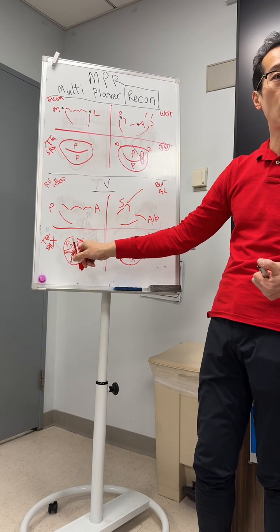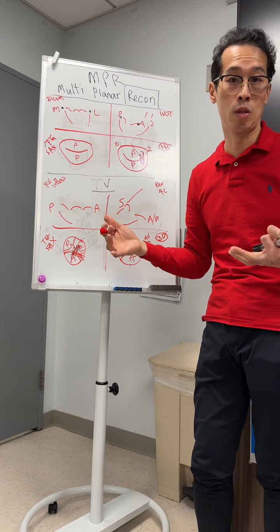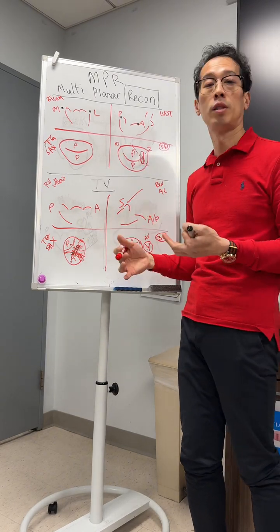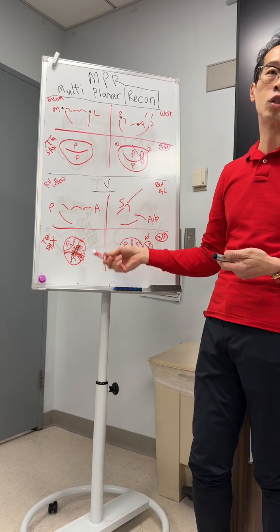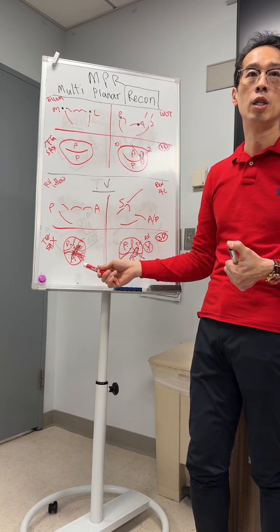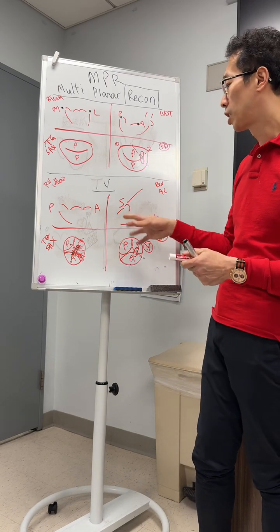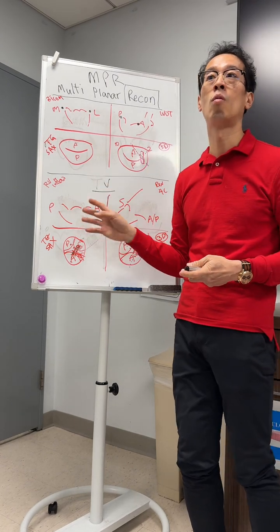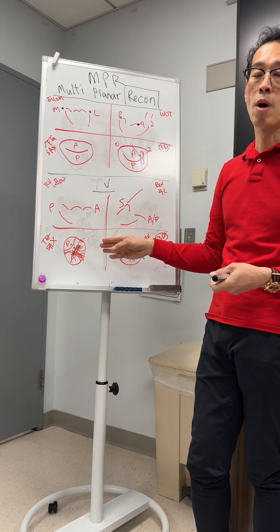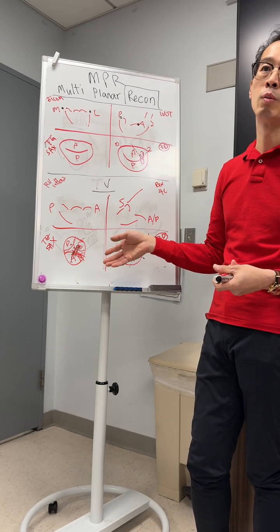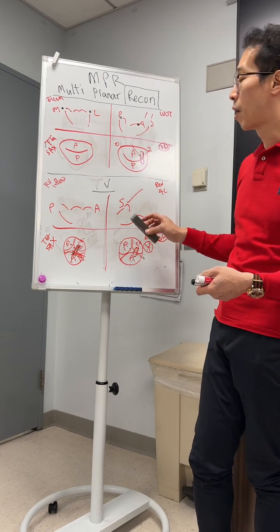Remember, you can use fluoroscopy to approximate the orientation, but not the actual exact orientation. You still have to adjust that. So only once your orientation is optimized, then you take the parallax on fluoro. So this is very important in terms of you don't want to misinterpret your orientation by thinking the device is already in the optimal configuration. So that's very important.